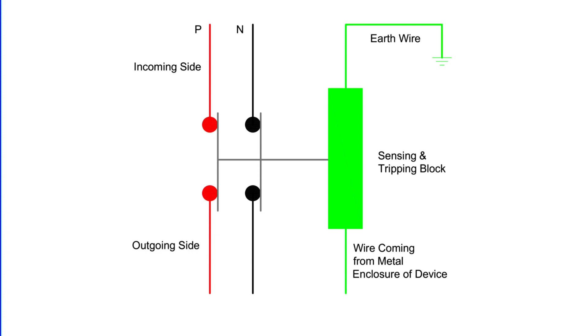Take an example of that outgoing red color wire accidentally having contact with the green color wire. This would result in a leakage of current between the phase wire and the green ground wire. As a result, a voltage drop develops across the tripping coil. This voltage drop is sufficient to activate the trip circuit causing the ELCB to disconnect or isolate the source from the fault.